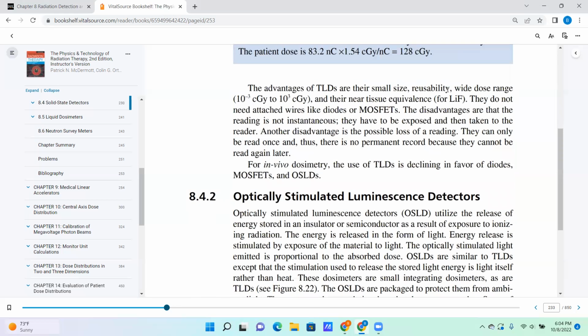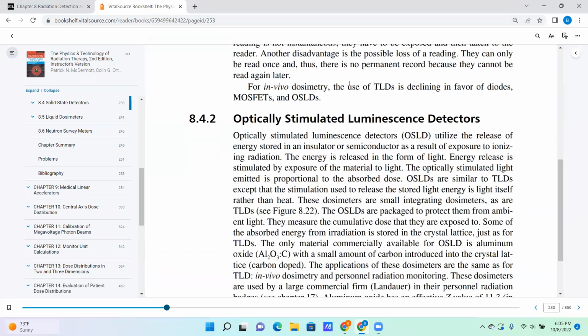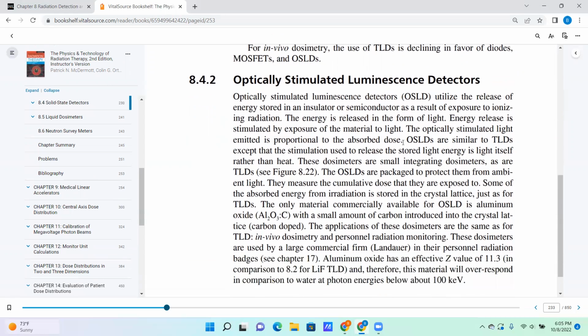They're small, they're reusable, and they have a wide dose range, and those are the advantages. And they are near tissue equivalent. They do not need attached wires like diodes or MOSFETs. The disadvantages are that the reading is not instantaneous. They have to be exposed and taken to the reader. Another disadvantage is the possible loss of a reading. They can only be read once, and thus there is no permanent record because it cannot be read again later. For in vivo, the use of TLDs is declining in favor of diodes, MOSFETs, and OSLDs, if your clinic has them.